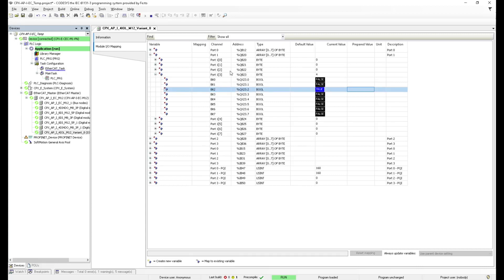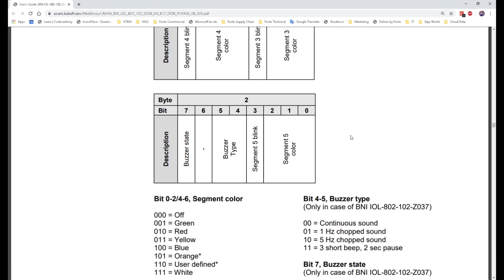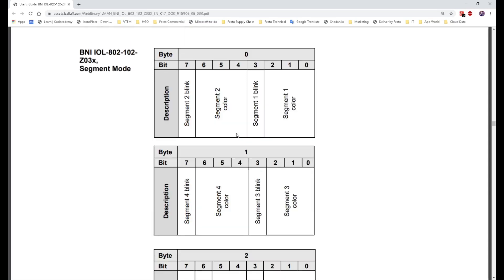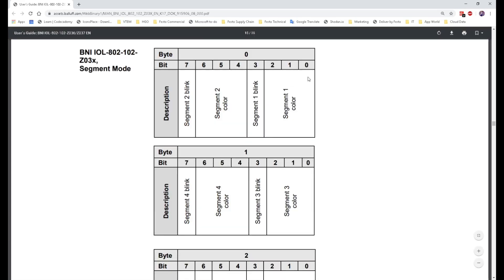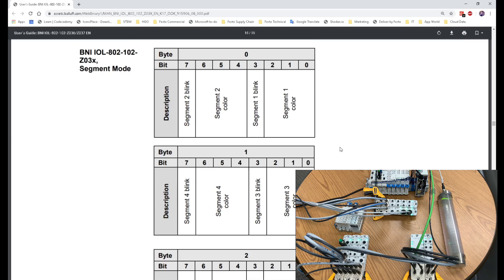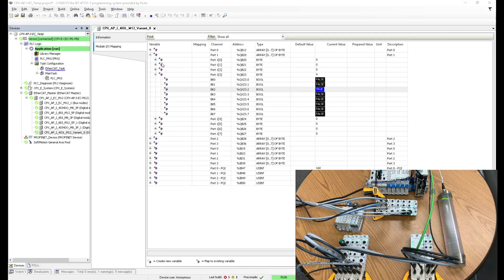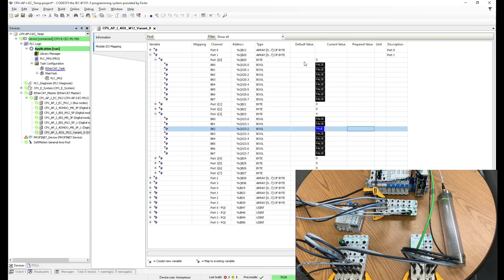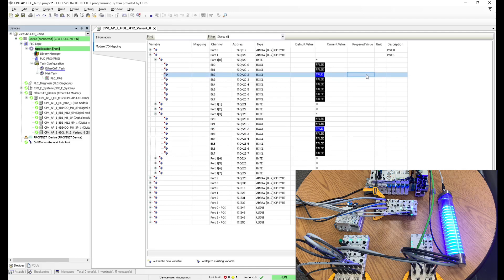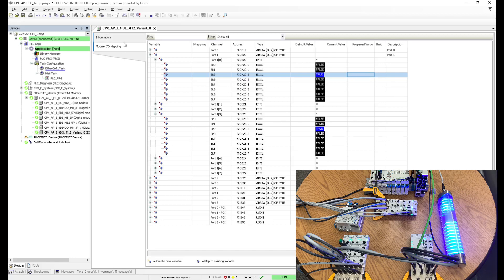And then we gotta switch on a color. So now we switch on a color, for example, on byte zero, we set this to let's say blue, which would be the third bit. Byte zero, bit two. This one right here. So now I have control over IO link of that stack light. So as you can see, it is very easy to set up this topology right here.